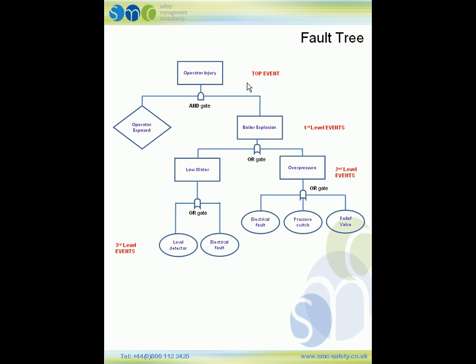So that is what your fault tree should look like. The main thing to remember is to make sure you have the operator exposed in the first level event. Now we apply the frequencies from the table. For condition A — the low water failure — the frequency for the level detector is 0.1 per year and for the electrical fault is 0.05 per year. Because this is an OR gate, we add the frequencies: 0.1 plus 0.05 gives a frequency of 0.15 per year.